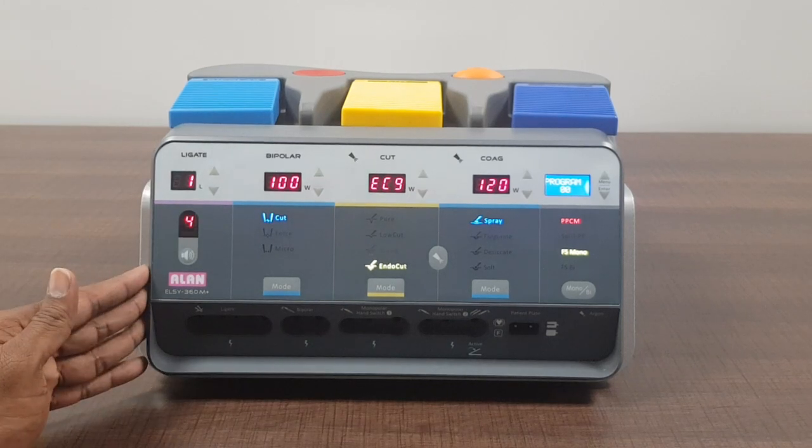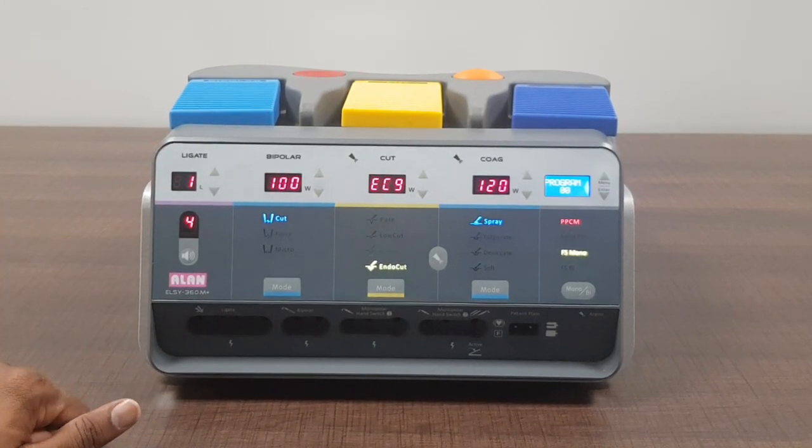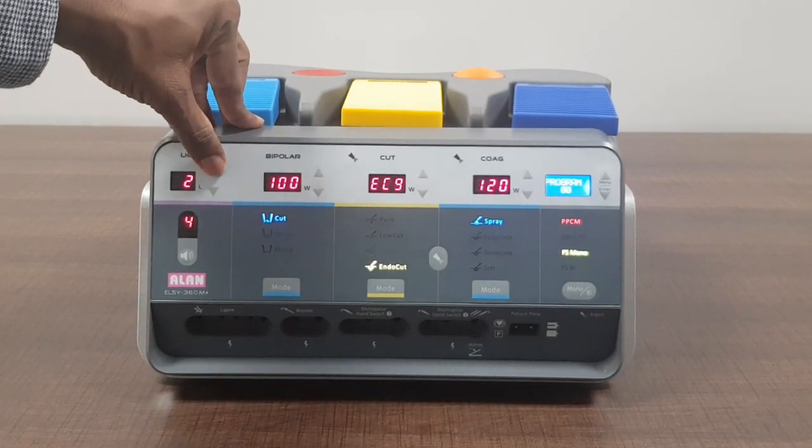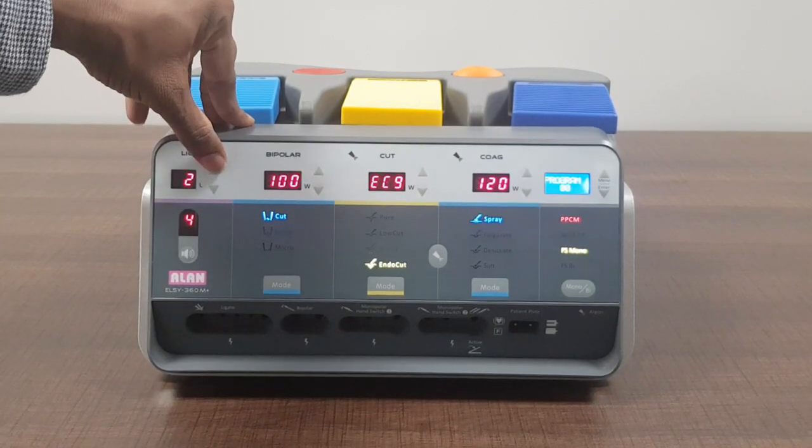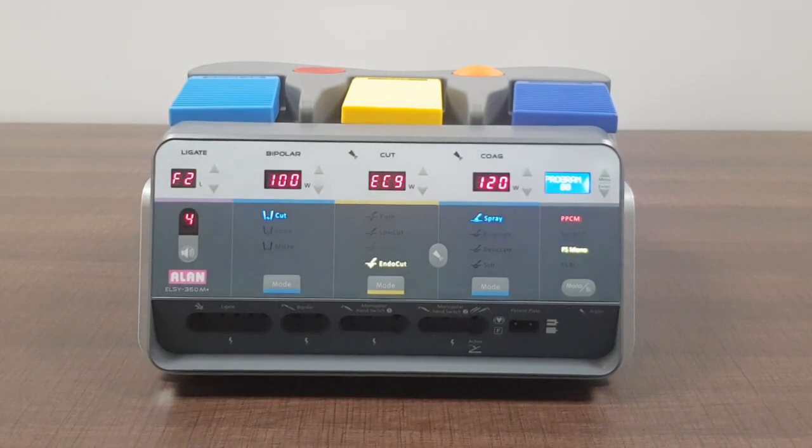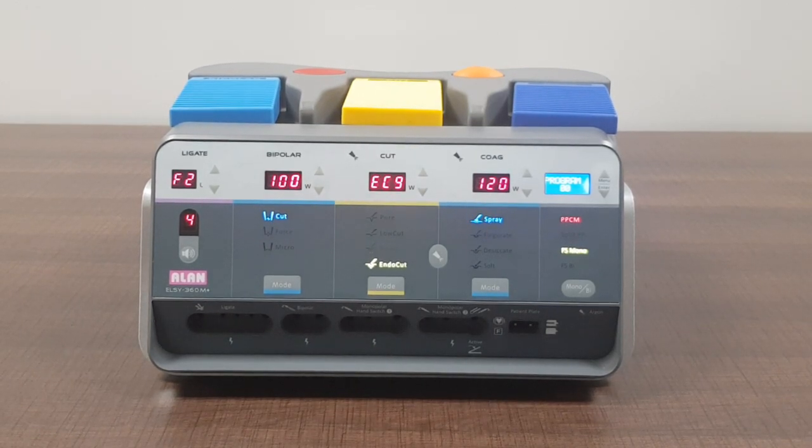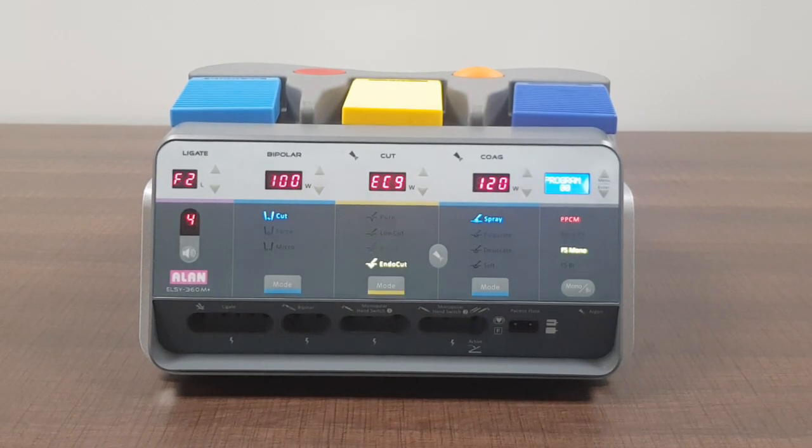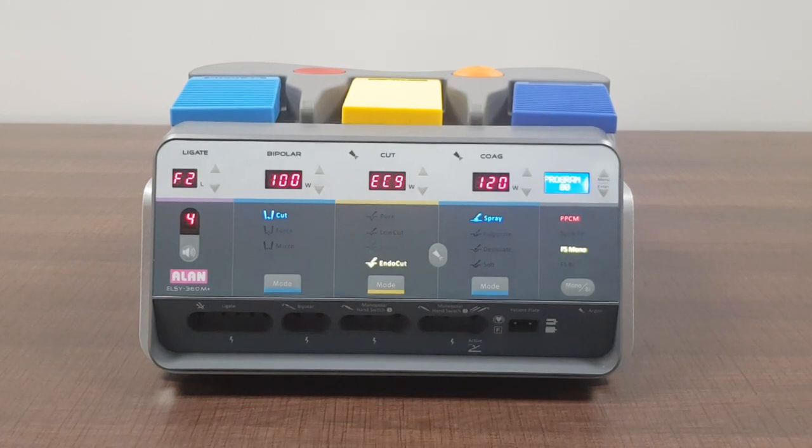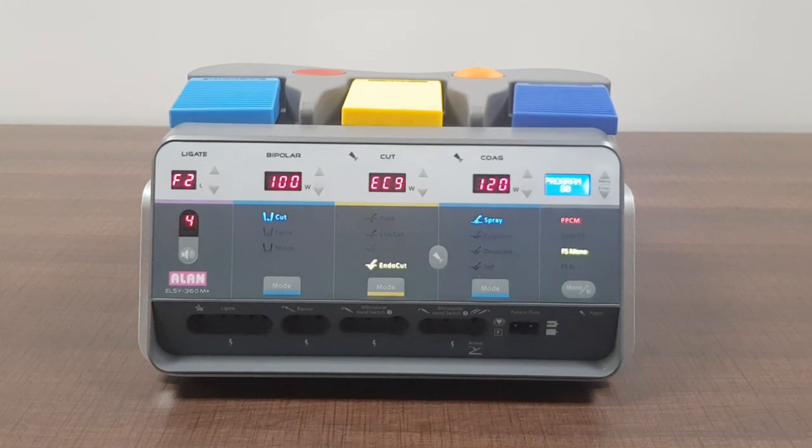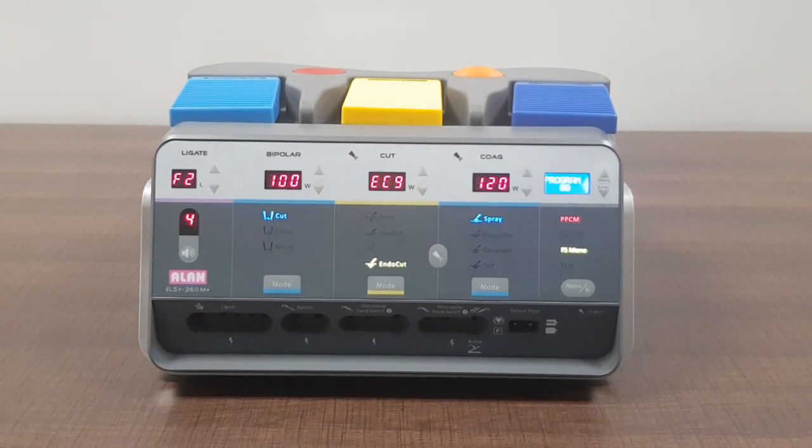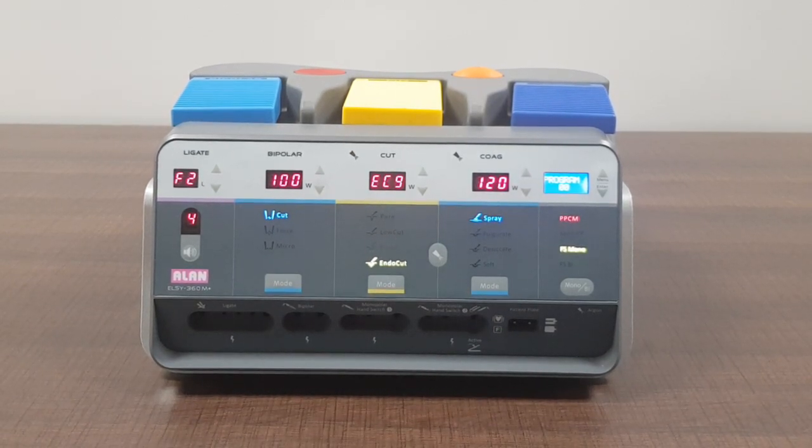So that was the feature for a basic cautery where you have monopolar cut, monopolar coag and bipolar. Now comes the most important feature for all the vets which is a ligate or most commonly most people just say it as ligature. Here we have seven levels. First five levels are for L1 to L5 and then comes F1 and F2. So overall total we have seven levels in that, L1 to L5 which has a different combination of current and voltage, and F1 and F2 has a very different current and voltage combination. If you remember we have used F2 in the surgeries and it gave better results than any other modes. So my suggestion would be to use F1 or F2 would be best for us.